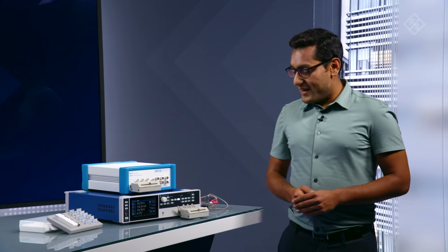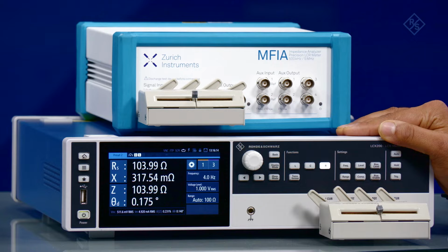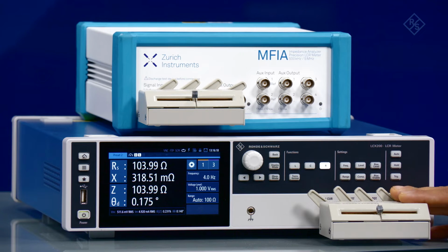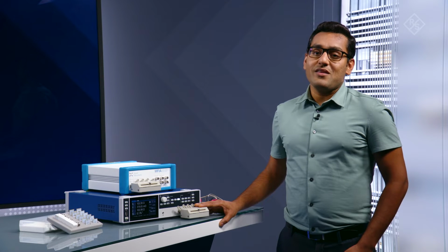This demo will help you determine the best instrument for impedance measurement. In this example, I have connected the test fixture LCX-Z1 to the LCX200. This fixture is ideal for lead type devices. My component under test is loaded into the spring-loaded insertion slots of the Z1 fixture.